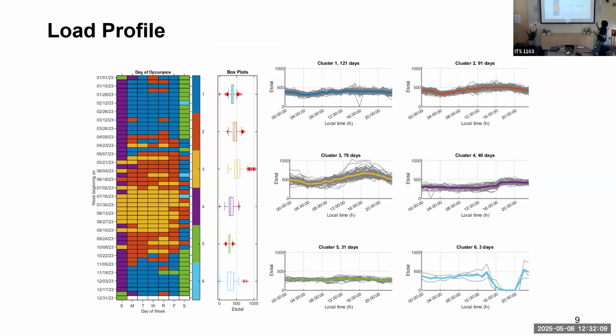If we start looking at these different clusters, let's take a look at the yellow one first. It is maybe during the summertime, July, maybe some August as well. Early in the morning, their facility is around 500 kW. But when they start production, when the outdoor temperature starts heating up, their load starts getting higher and higher. And if you look at that 4 to 9 period, it looks like that's when their peak load is also happening. So this is how typical refrigeration facilities are operating in California.